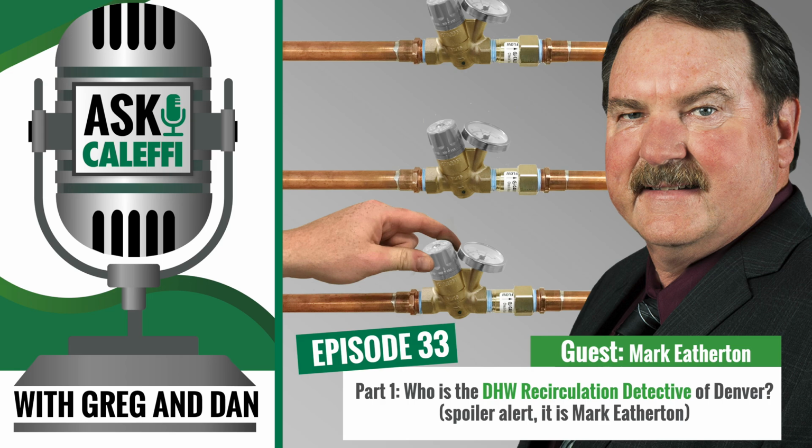And the first thing I will do is grab the circulation return. And if the circulation return is ice cold, I know I've got cold water charging backwards through that circ return and going to the top floor. And at the top floor, they've got hot and cold water coming from 2 different positions. And it will also result in a shower temperature that's like a roller coaster ride. Starts out hot, goes cold, goes hot, goes cold. And the poor consumer is standing there the whole time making adjustments to their shower valve.